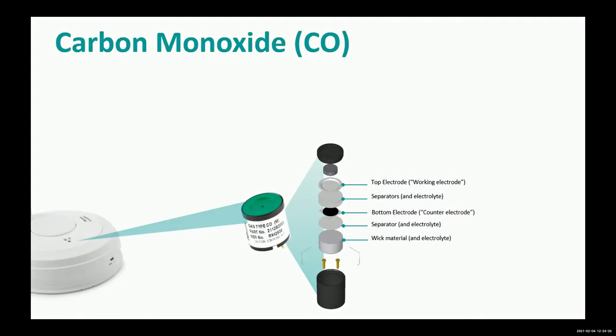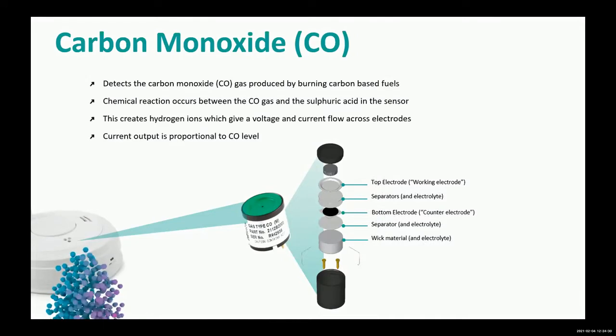So again, it's a chemical reaction that takes place within this chamber or the sensor itself. When it detects the carbon monoxide, that's the gas produced by carbon-based fuels, a chemical reaction occurs between the CO gas and the sulfuric acid. This creates hydrogen ions, which give off a voltage and a current flow across the electrodes. That current output is proportional to the CO level within the atmosphere. So if that unit produces 4 microamps of current, that equates to 100 parts per million of carbon monoxide present in the atmosphere. So it's a very, very accurate way of measuring the atmosphere for carbon monoxide levels.